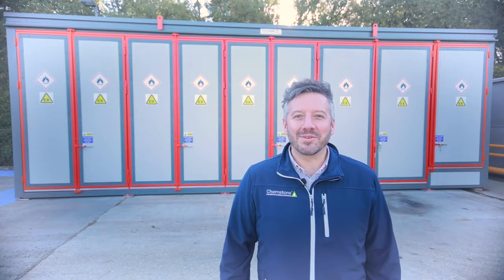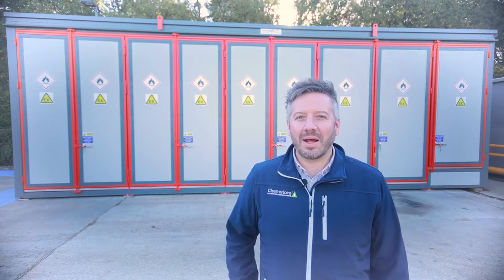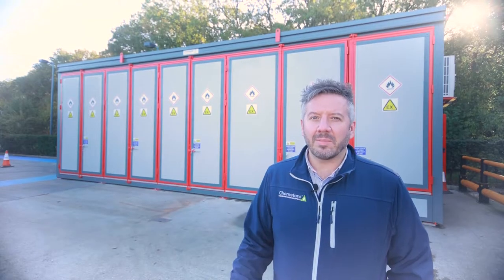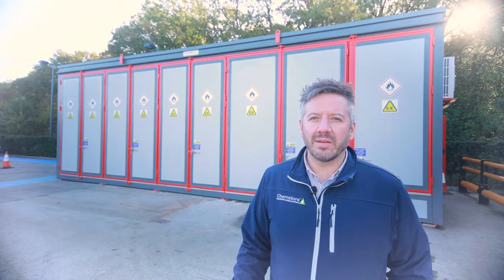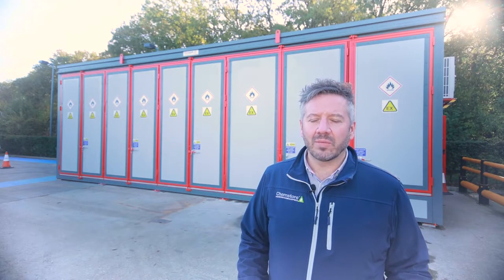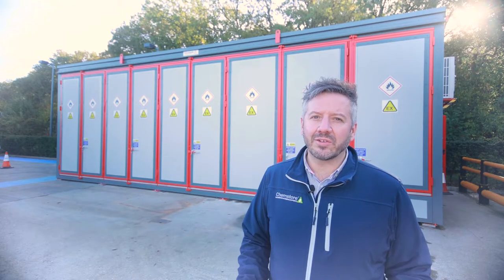Hi, I'm Mike Brody from ChemStore, and I'm here to talk to you today about our brand new state-of-the-art lithium-ion battery storage facility we've just installed. Lithium-ion batteries have the ability to go into thermal runaway. This can be caused by three events: mechanical damage, overcharging, or a defect in the battery during the manufacturing process.